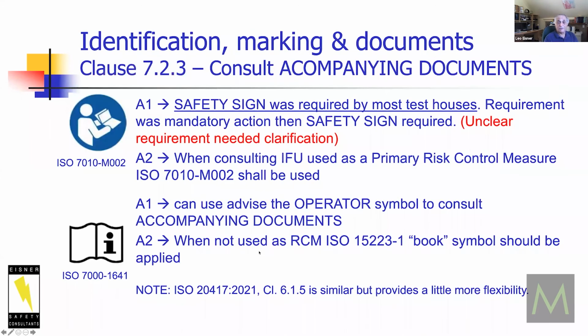That's really the difference. So this symbol was almost unofficially mandated and forced on manufacturers to use as 'read IFU' instead of being a primary risk mitigator. If you're using the symbol for a primary risk control measure, then you should be using it, which is the clarification in Amendment 2. Now in Amendment 2, if you're not using it as a risk control measure, you're allowed to use this one instead.